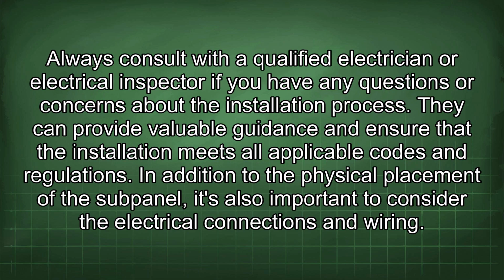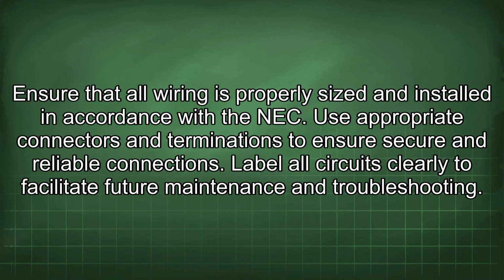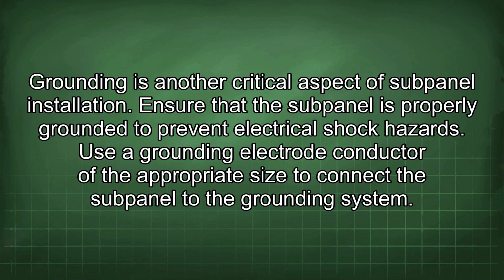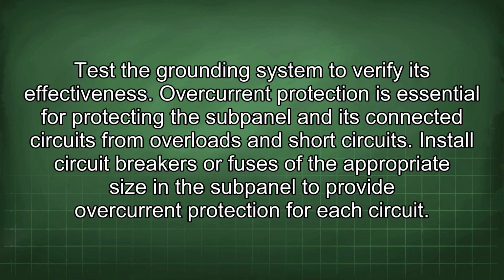In addition to the physical placement of the subpanel, it's also important to consider the electrical connections and wiring. Ensure that all wiring is properly sized and installed in accordance with the NEC. Use appropriate connectors and terminations to ensure secure and reliable connections. Label all circuits clearly to facilitate future maintenance and troubleshooting. Grounding is another critical aspect of subpanel installation. Ensure that the subpanel is properly grounded to prevent electrical shock hazards. Use a grounding electrode conductor of the appropriate size to connect the subpanel to the grounding system. Test the grounding system to verify its effectiveness.